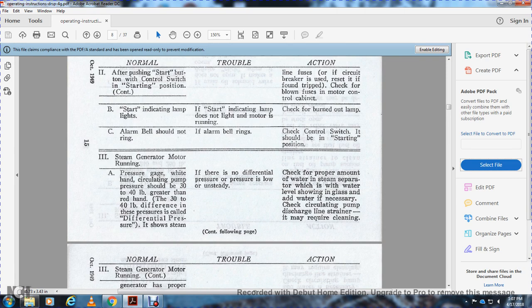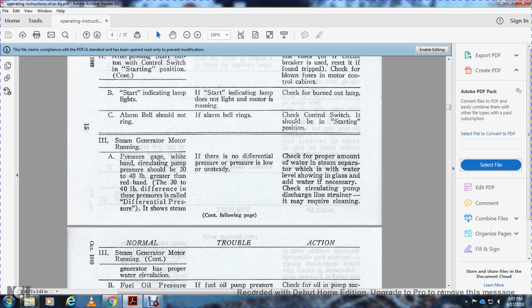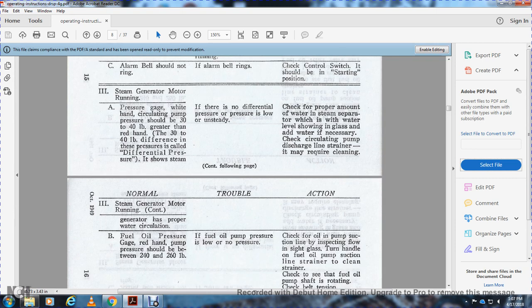Three, your steam generator motor. A, on the pressure gauge, the white hand, circulating pump pressure, should be 30 to 40 pounds greater than the red hand. The 30 to 40 pound difference in pressure is called the differential pressure. It shows steam generation has proper water circulation. If there is no differential pressure, or the pressure is low or unsteady, check for the proper amount of water in the steam separator, with the water level showing in the glass, and check the circulating pump discharge line strainer. It may require cleaning.